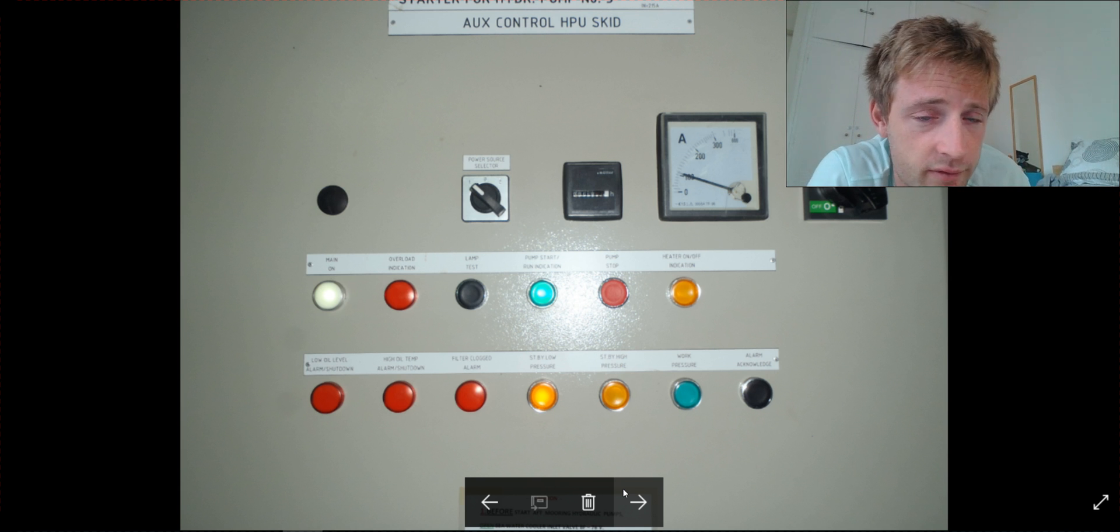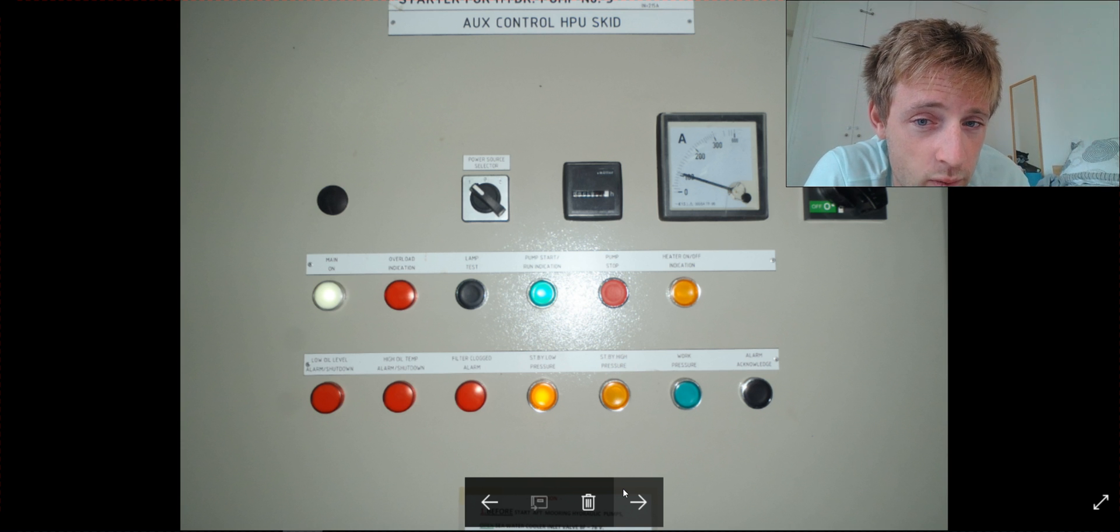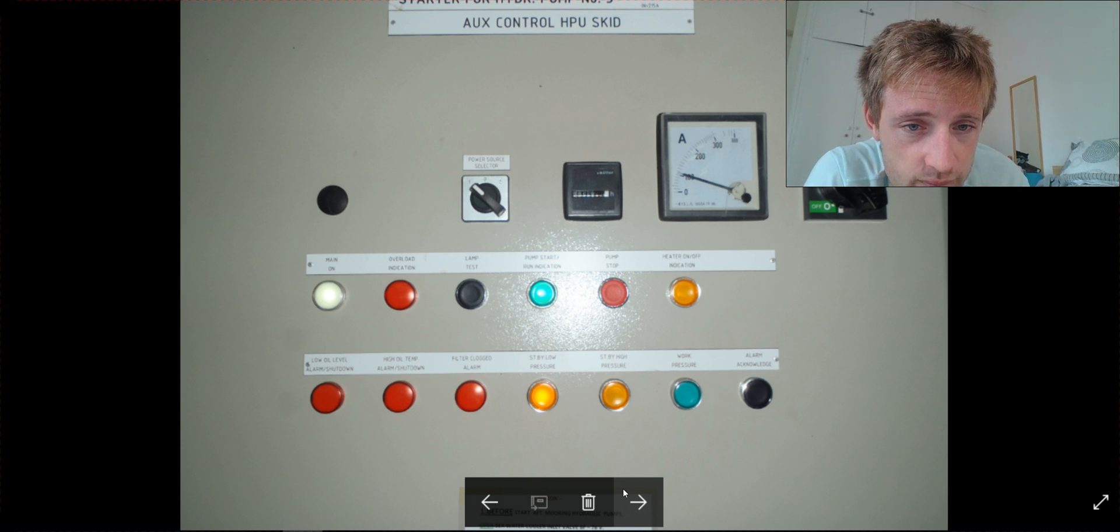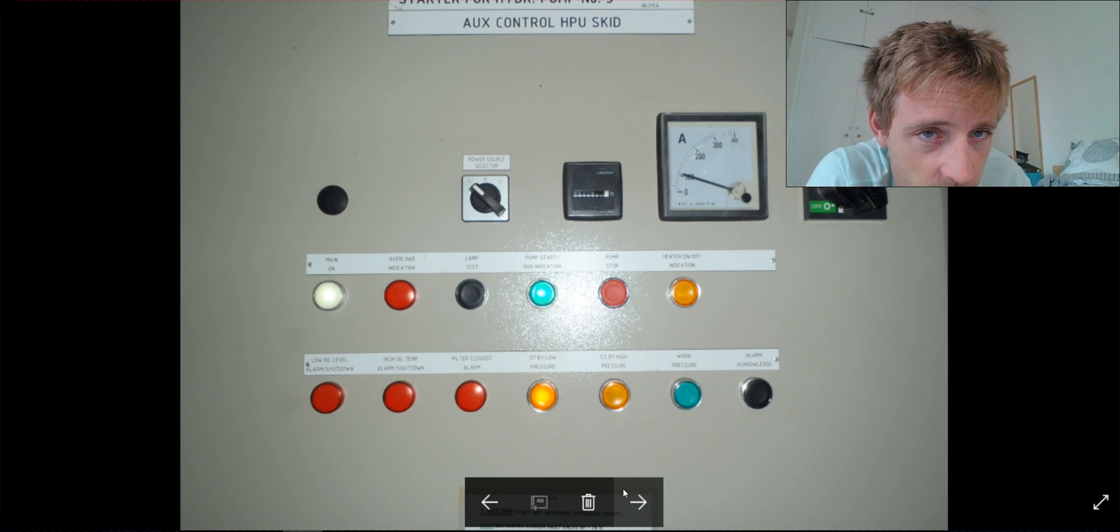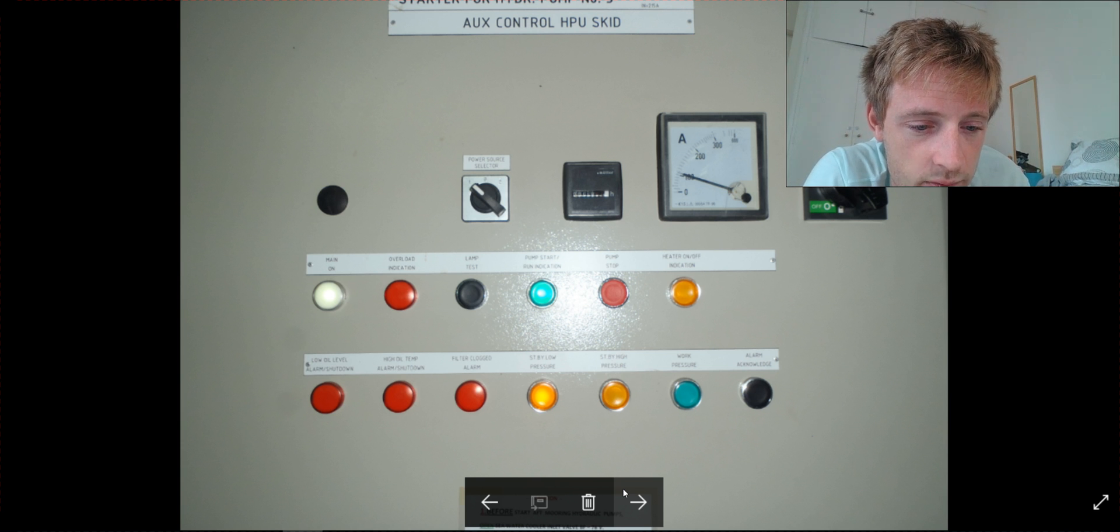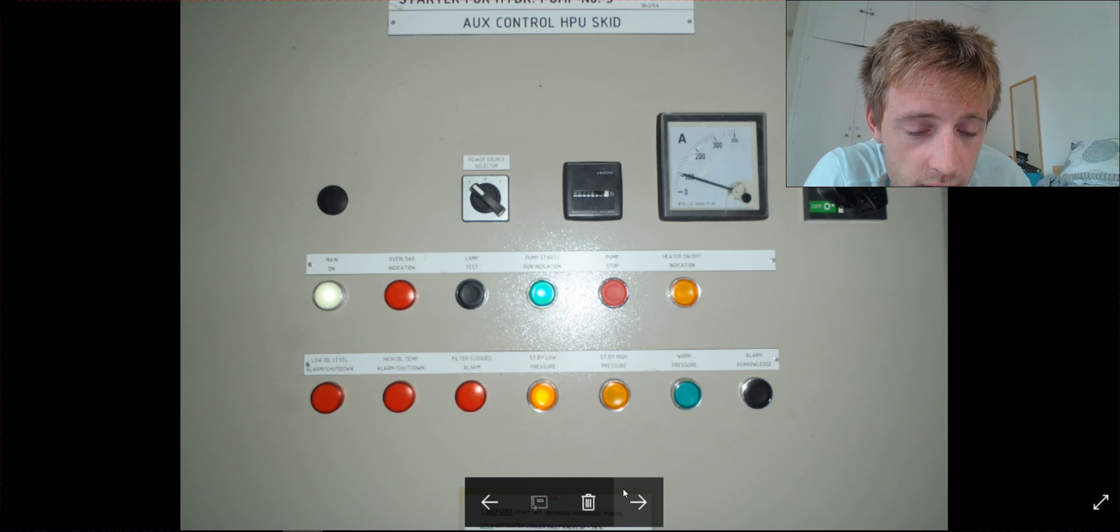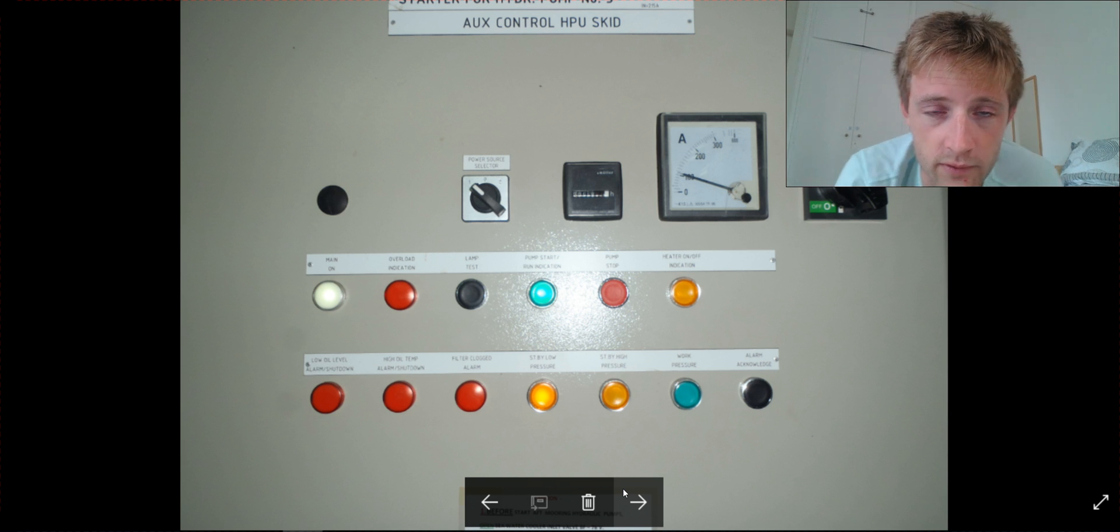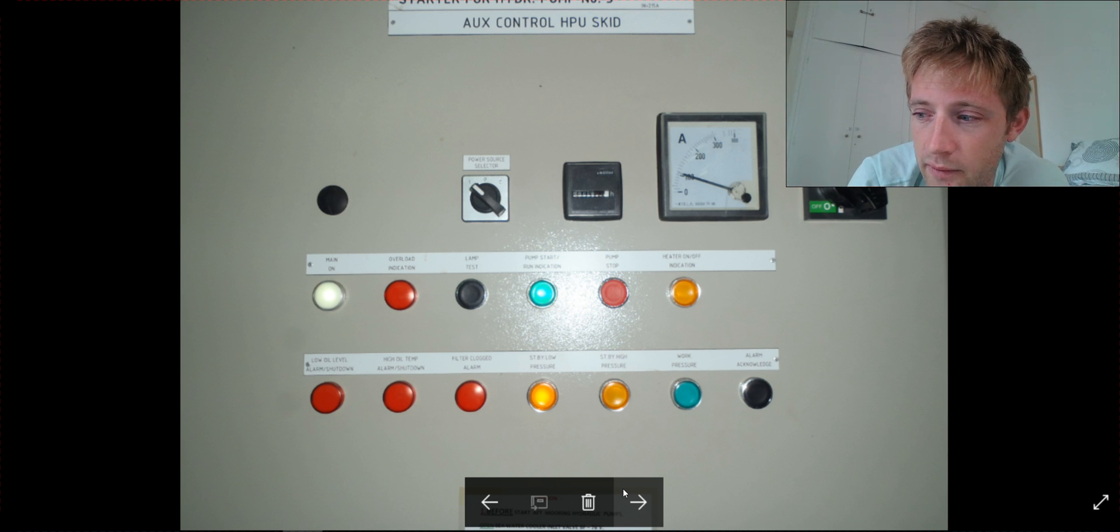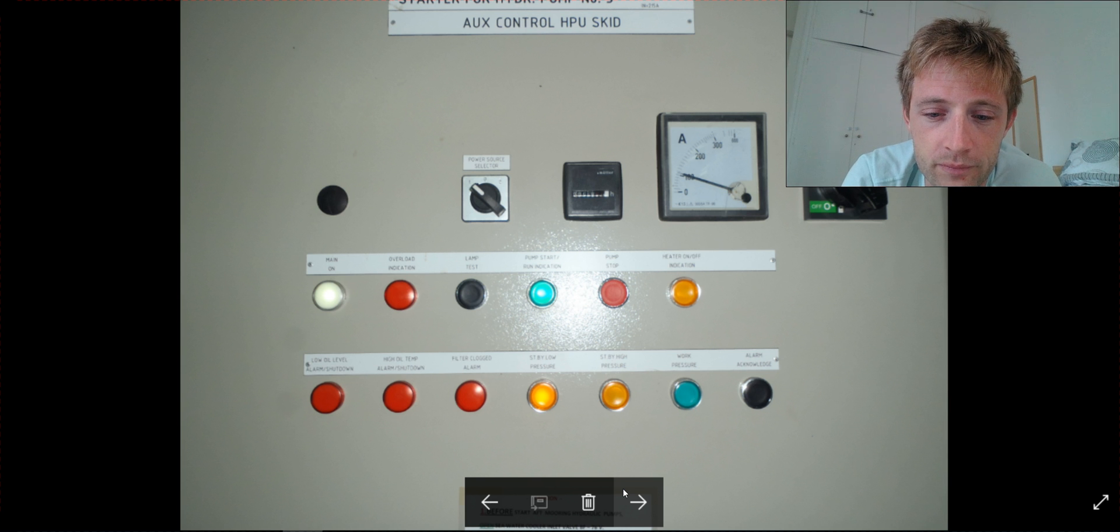Also, you will observe any vibrations. Then you will check the temperatures, but the temperatures you can see at the load where the system is at the load. Very important is the noise, that you didn't hear something strange. This is the most important.